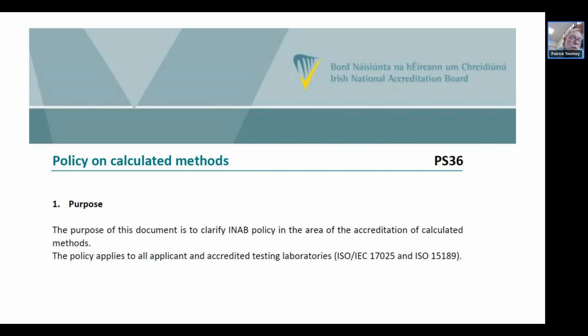Amongst other ISO standards, they assess us on 15189 for medical laboratories, and they have a policy on calculated methods. It's very, very reasonable, but bear in mind anyone can produce a calculation. They don't have to be in the laboratory. It is how robust it is. Have they verified the data using an independent data set, for example? Have they even calculated correctly?